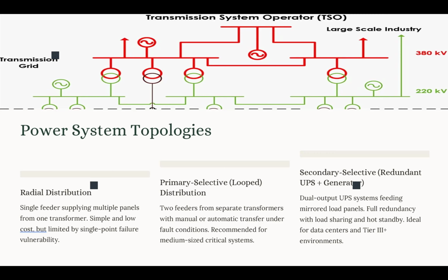These secondary selective systems are automated, so they have automatic instantaneous transfer when we have a failure in one of the sources, and are normally used in a mission critical environment when we have sensitive electronic equipment. Now, we said there is an advantage. We have a full redundancy that makes sure of continuous uptime. We support load sharing in this configuration and hot maintenance. So if we have to do maintenance, we don't need to eliminate all the sources. We only de-energize the specific part that we want to do the maintenance on, while the rest of the system is still working in a nominal operational condition.